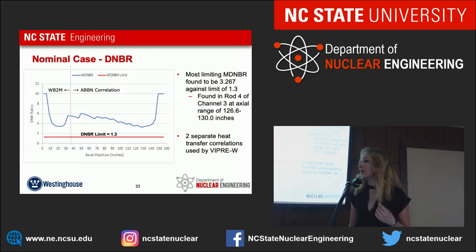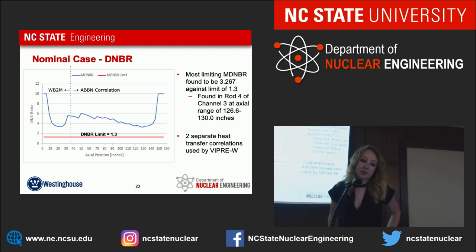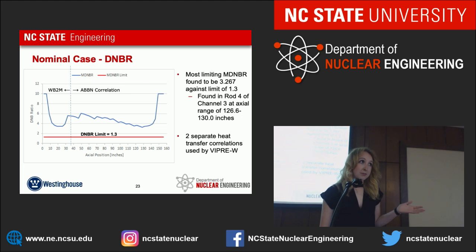Here you can see our minimum DNBR axially for our nominal case. The minimum was 3.267, which you can see is in the axial range of 126.6 to 130 inches. And that is well above the limit for DNBR that we were given of 1.3.